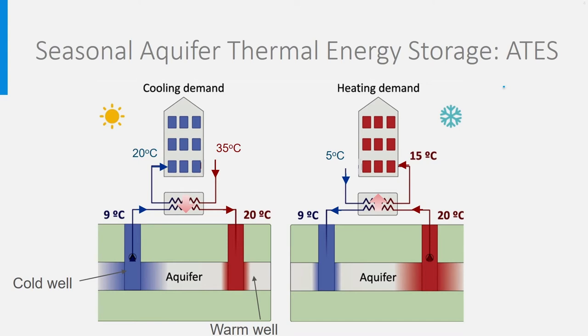It is also mandatory to make sure and demonstrate that there is a thermal balance in the ground, meaning that the quantity of heat extracted is the same as the quantity of heat supplied to the ground.